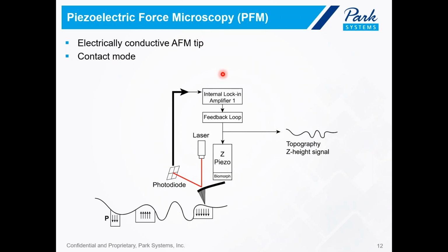The schematic here shows how a topography signal is generated in contact mode. We have a laser that hits the back of the cantilever and is reflected to a position-sensitive photodiode detector. The AFM tip is raster scanned across the sample, and changes in the sample topography produce changes in the laser position on the photodiode. This signal passes to a lock-in amplifier and through a feedback loop, and eventually to our Z piezo to keep the force at the tip-sample contact point constant. So this is how we would get the topography signal in contact mode.